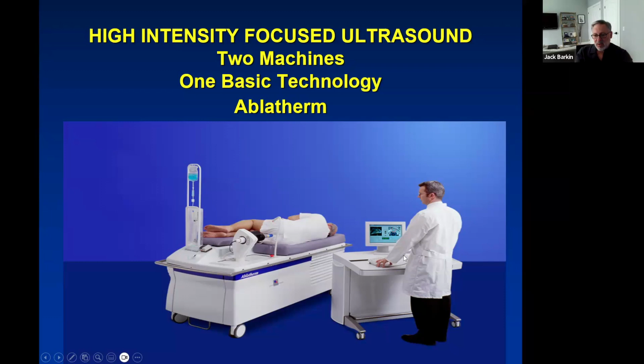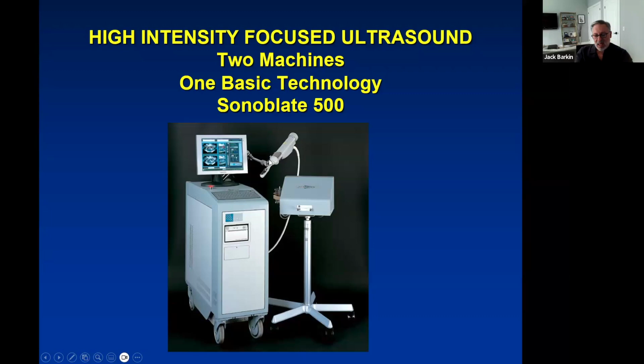The machine that I've been using from day one, and I had the choice of both, and I chose this one, is actually an American machine called the SonaCare machine, or Sonablate, which is produced in the United States, even though until 2018 it wasn't actually approved in the United States. So about 12 or 16 years after we were approved in Canada. It's a much more mobile, much smaller machine. The screen is combined with the actual module that provides the treatment. And this is what's called our chiller, which delivers chilled water through the probe itself on a continuous basis to help cool the rectum. And it has an arm that stabilizes it.